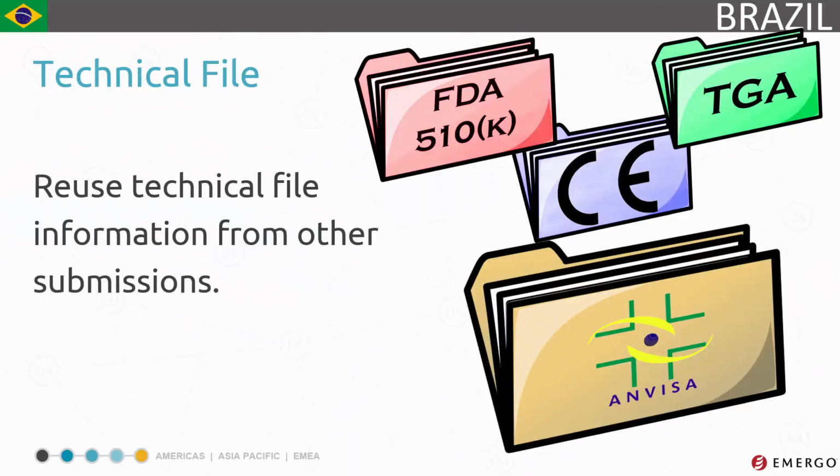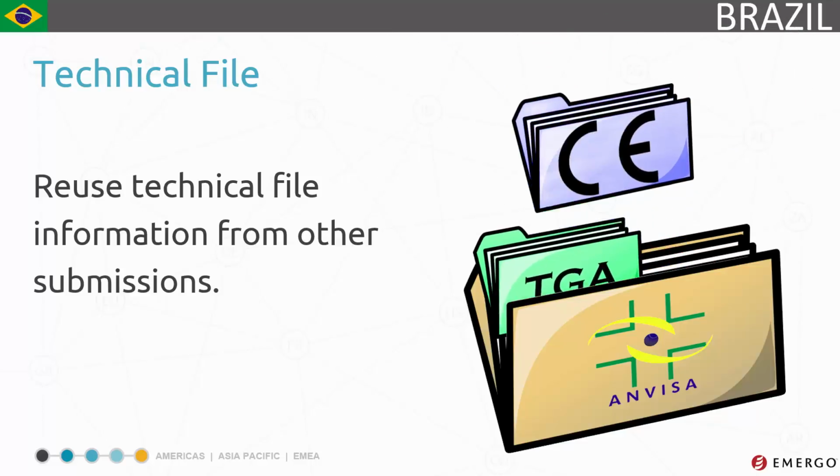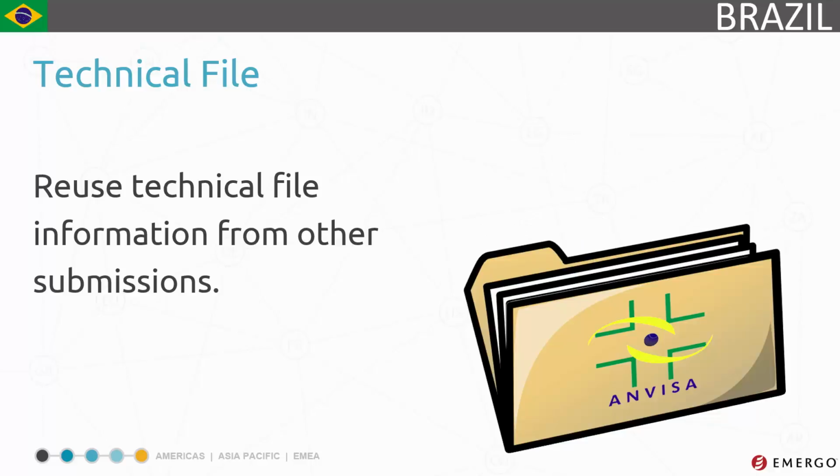Already marketing your device in other countries? Brazil doesn't require you to reinvent the wheel. Manufacturers that already have prepared technical files for CE marking, US FDA 510(k) clearance, or many other regulatory processes may usually reuse portions of that information to prepare their Brazilian technical files.